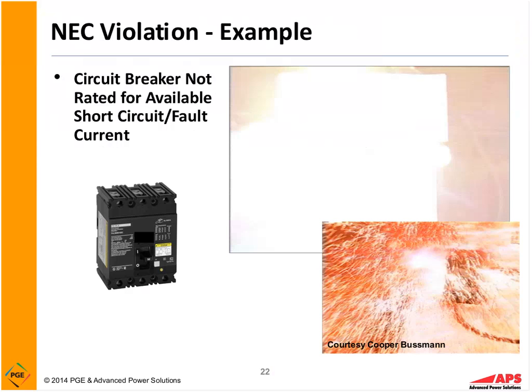So we can look at this NEC violation here. We have a circuit breaker not rated for the available fault current. In other words, there's too much current flowing through it from the system when there's a fault downstream, whether a hot conductor, an energized conductor, gets pinched to ground, or phase to phase, or phase to neutral. So if we have conductors that make connections that aren't supposed to be there and the device is not properly rated to interrupt that current, it can actually cause that device to explode, which is a hazard in itself.